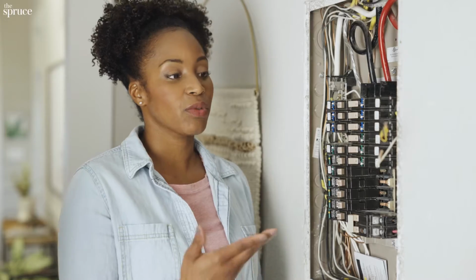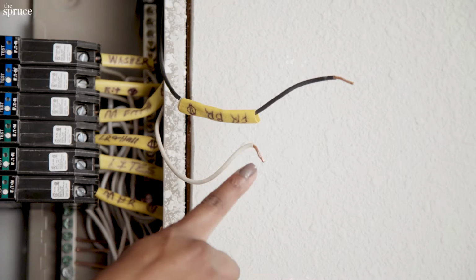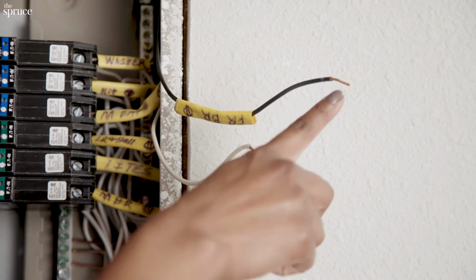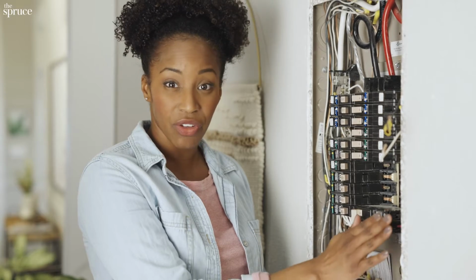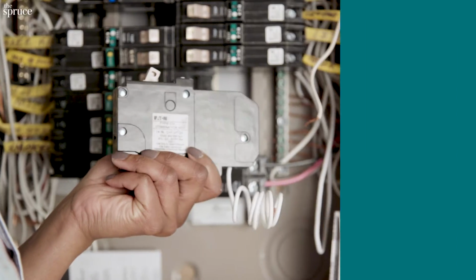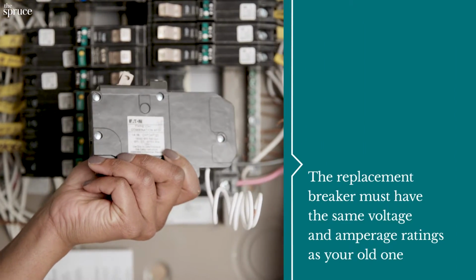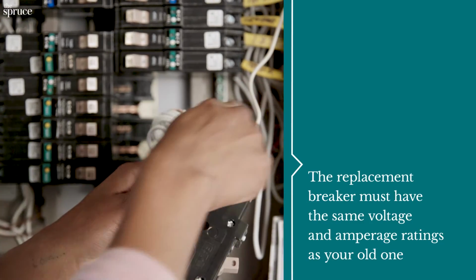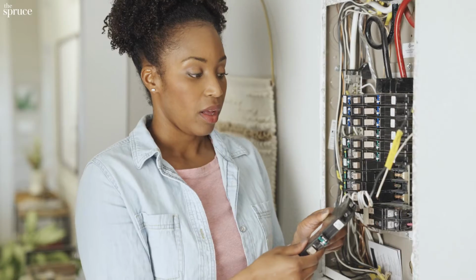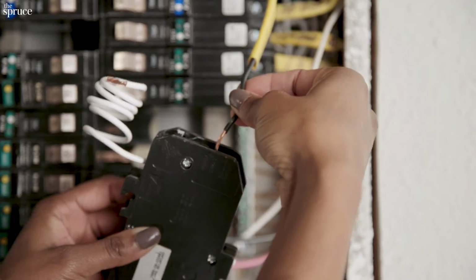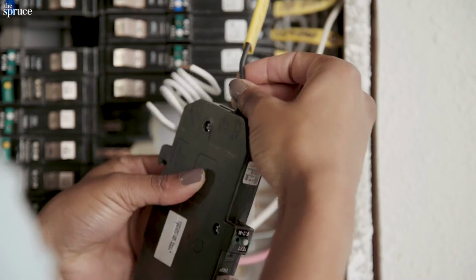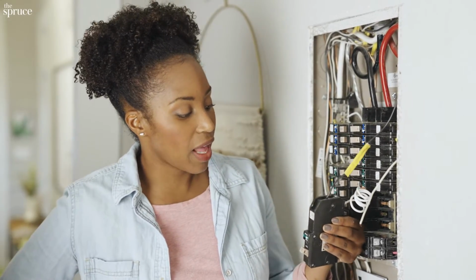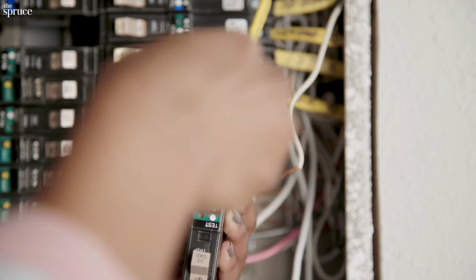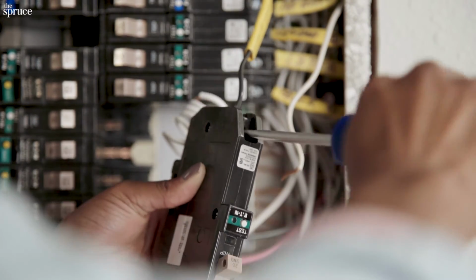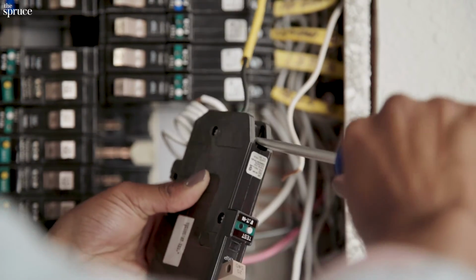If you don't intend to replace the circuit breaker, then make sure you cap the ends of the wires and tuck them away in the panel, making sure they're not touching anything. I'm installing an AFCI circuit breaker, so I'll be using both hot and neutral wires. The first thing I'm going to do is install my hot wire and use a flathead screwdriver to tighten the screw, making sure it's really tight.